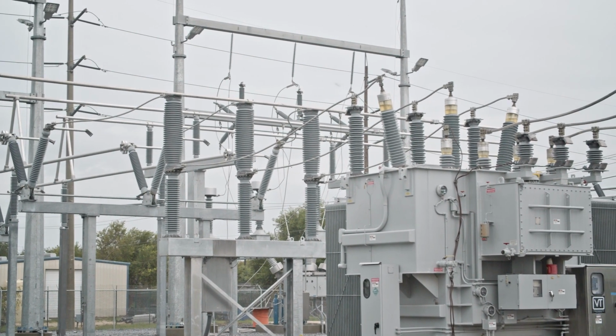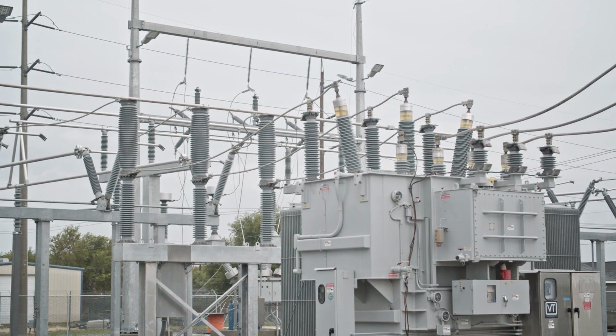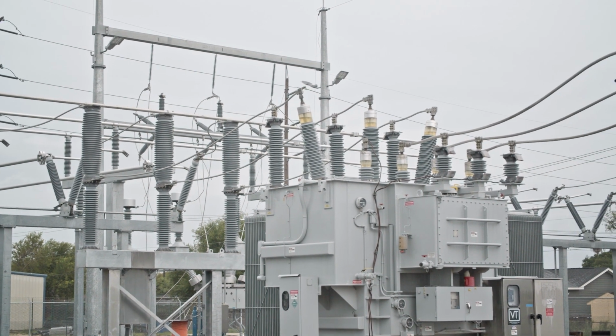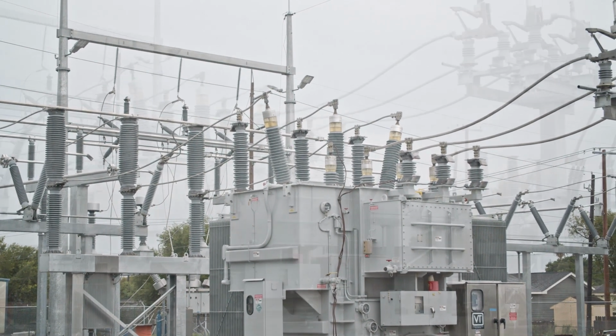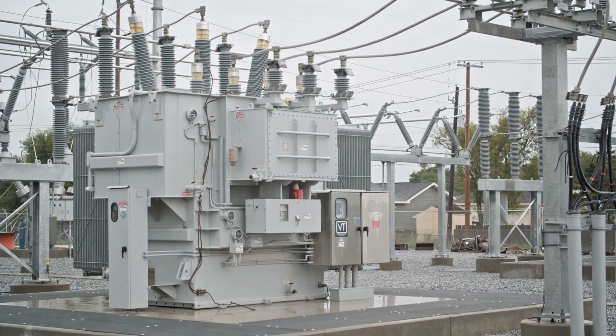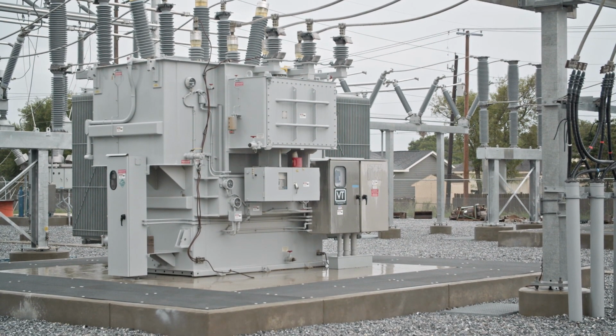This is a brand new state-of-the-art substation. We've got two transformers that are 28 megawatts each, which is 28 million watts, probably enough for between 1,500 and 2,000 houses per transformer. So potentially this station could run a significant amount of the community. For a city the size of Brownsville, this is our 16th substation, which gives you an idea of how we distribute power.